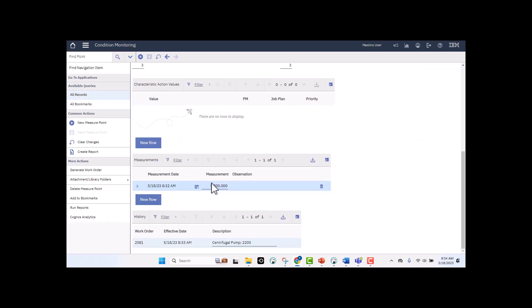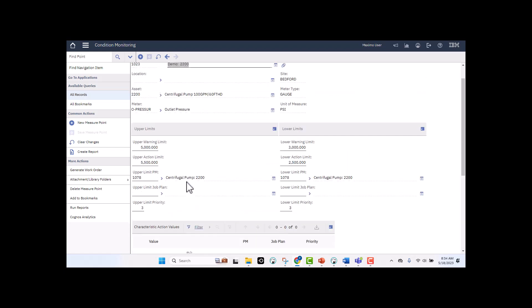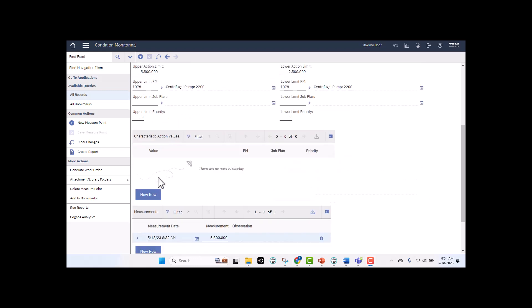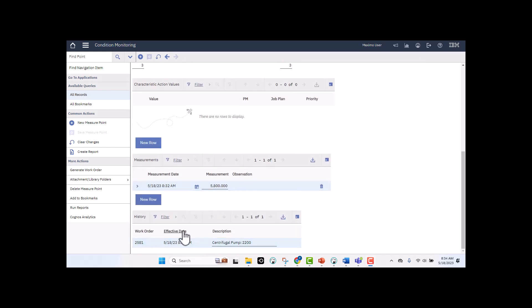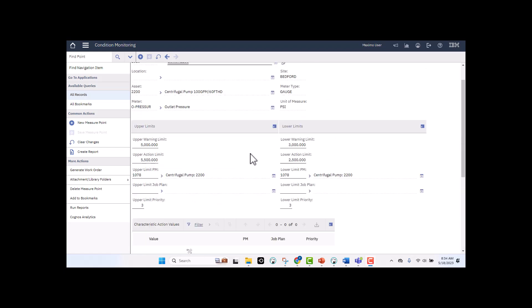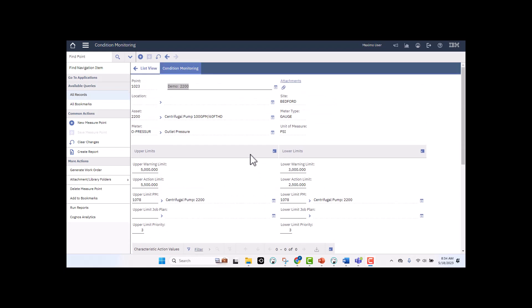So again, this is the value that I had input, 5800. And now when the cron task ran and it was able to pick up that value, there's sometimes a time lapse there. And it picked up that this value exceeded the upper control limit, the upper action limit, 5500. I put in 5800, so it generated a work order. So I did this all live time. It's really exciting to see how powerful condition monitoring functionality is, but also how easy it is to set up. So with that, I'd like to thank you very much for your time.